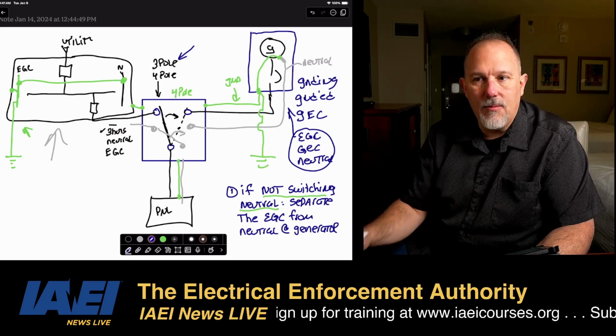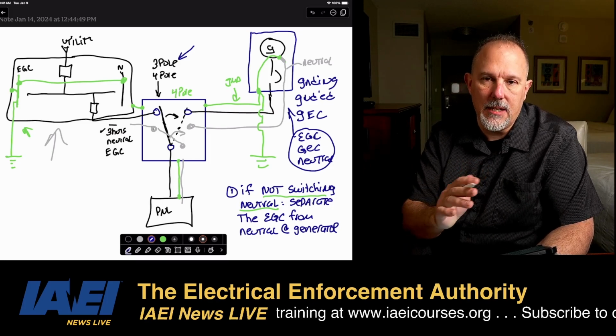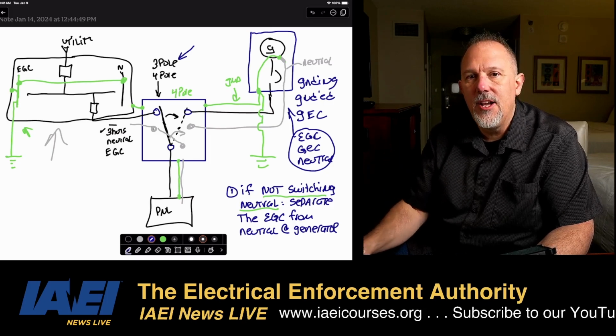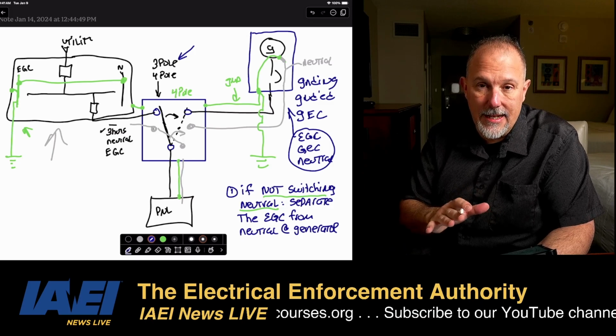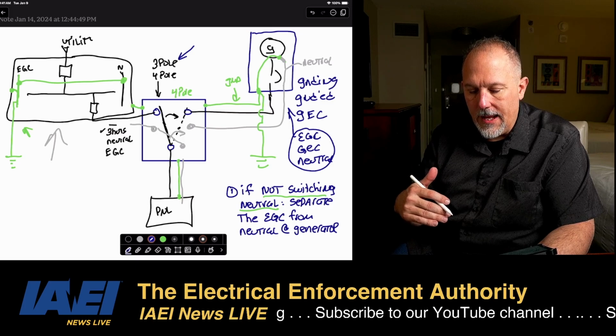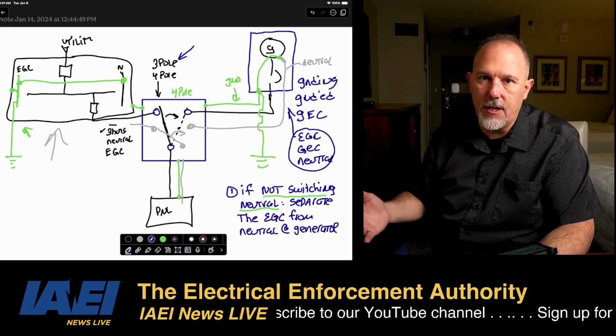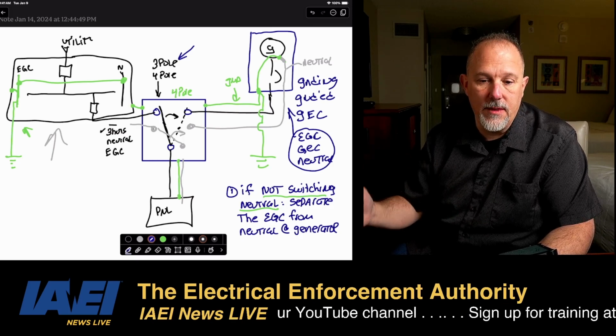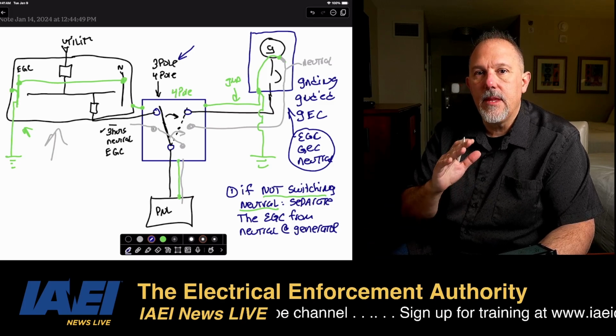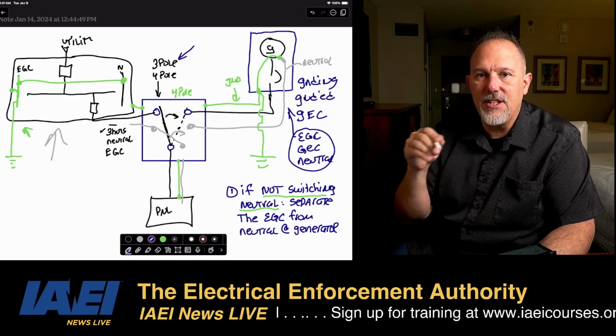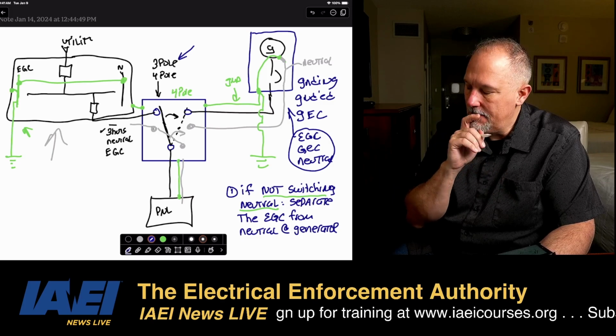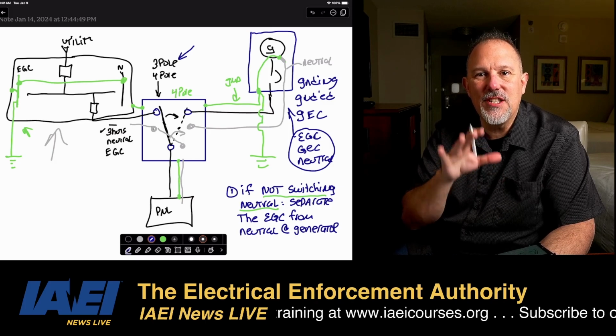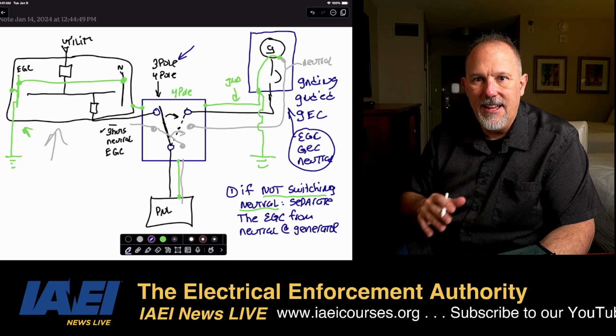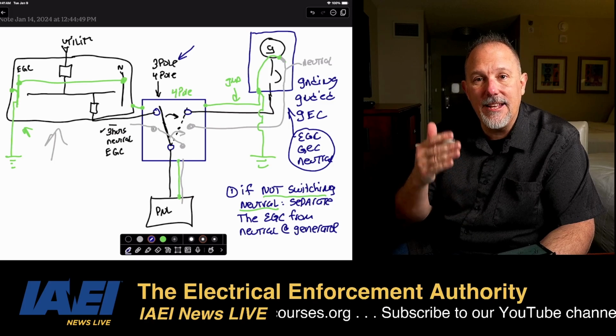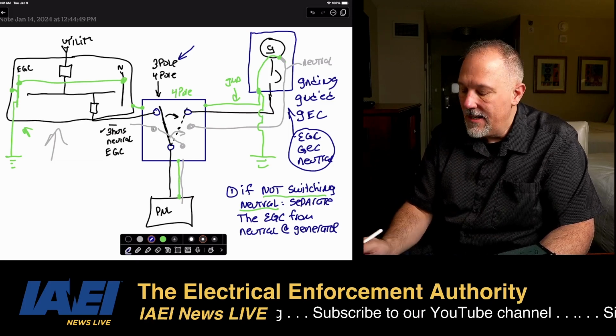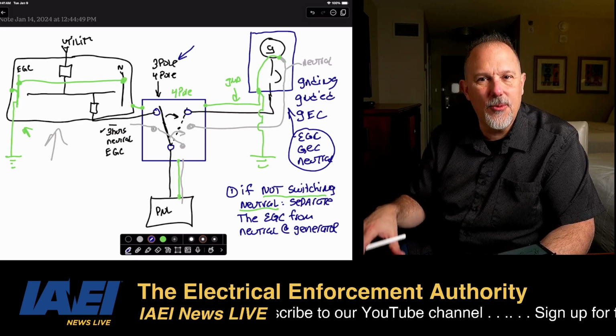He was thinking, well, we're going to need to buy a new transfer switch. They're going to have to buy a 4-pole transfer switch. When in reality, all they needed to do, and which is what they did, was disconnect the bond between the neutral and the ground inside the generator. It's okay to drive a rod for a generator and bond it for whatever reason you want. It's not a code requirement, but you can. Then I pulled up the instructions for that generator. I can't remember what brand it was, but the instructions say, if this is not a separately derived system, then remove the bonding strap. There were instructions and diagrams on exactly what to remove, and it was perfect. The manufacturer of that generator did a great job in their instructions.